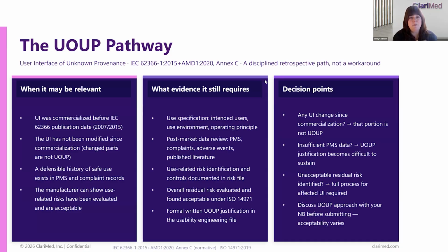But I have seen a significant amount of pushback on it throughout the different submissions that I've made, and a lot of variability in its acceptance. But I suppose the key to success is to demonstrate that the product under consideration is safe and effective for use, and that should be evidenced by a lack of use-related issues in market, which demonstrate that your user interface mitigations are effective in preventing use error. But if your post-market data is insufficient or the product user interface has changed, then it's probably going to be very difficult to provide it as evidence.